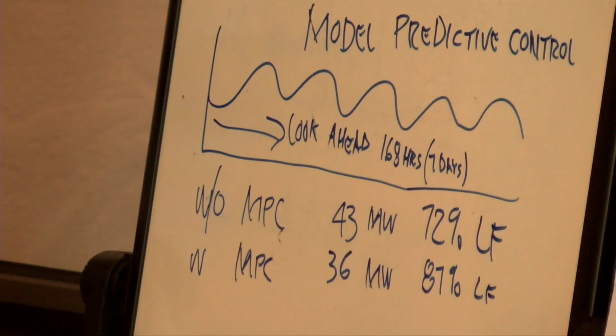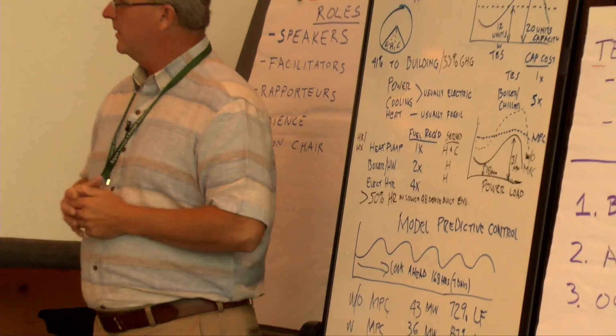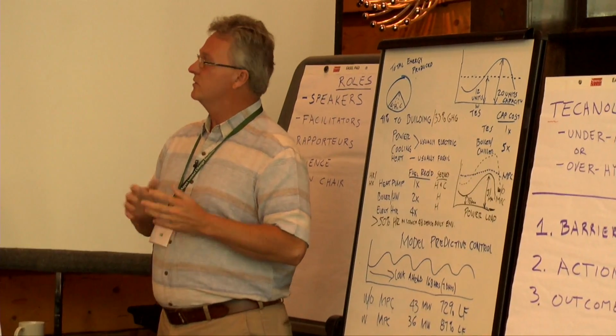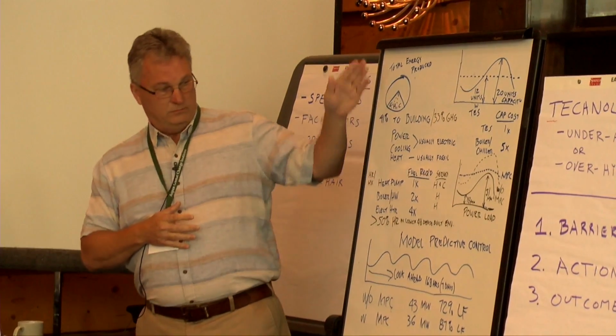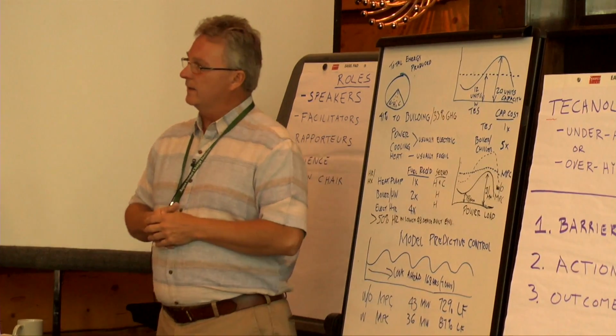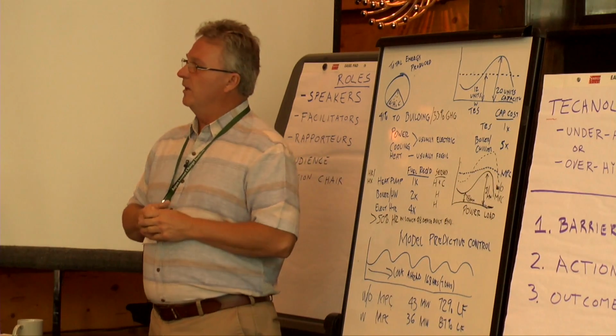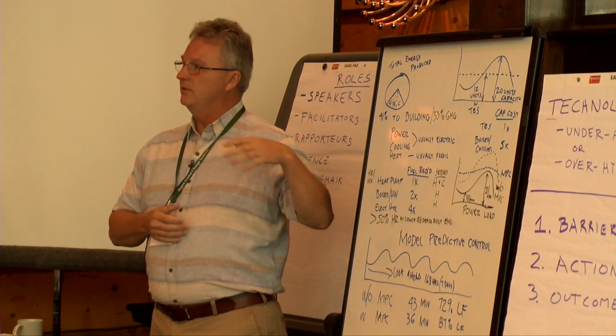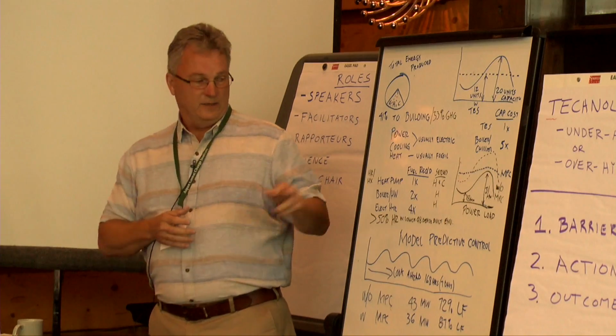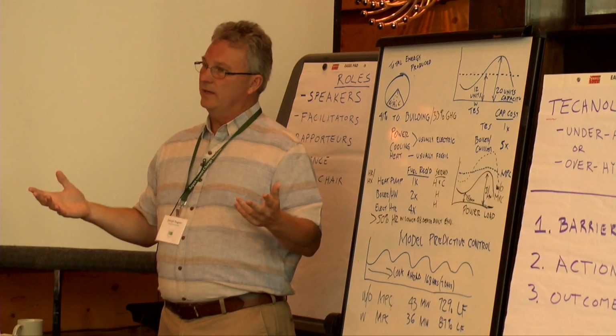And in our case, that's between $500,000 and $1 million a year, lower energy cost due to demand and commodity pricing. So you not only get a much more efficient footprint on the grid, you save a whole lot of money. So to summarize all the benefits, I would say it's probably most practical to electrify heating, cooling, and power for buildings. Deploy heat pumps to provide the heat component of it. Use recovered heat first, ground source heat exchange or water source heat exchange second. Employ both hot and cold thermal storage in the form of water, not steam or ice.